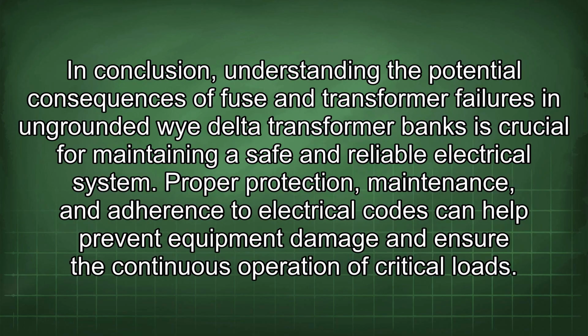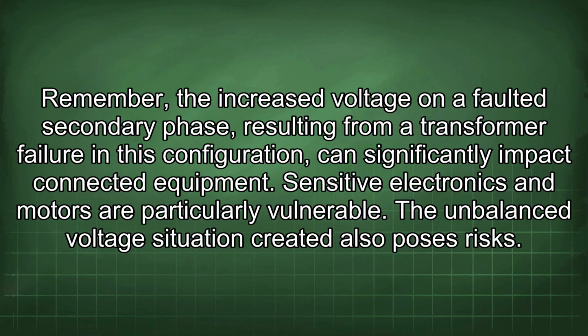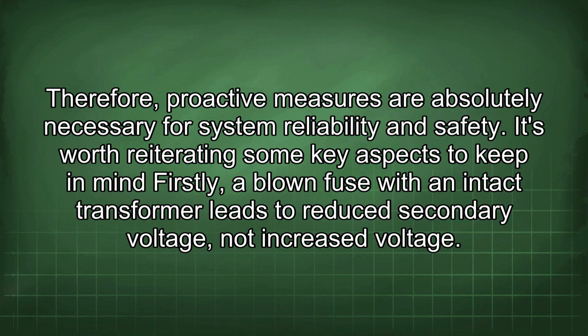In conclusion, understanding the potential consequences of fuse and transformer failures in ungrounded Wye delta transformer banks is crucial for maintaining a safe and reliable electrical system. Proper protection, maintenance, and adherence to electrical codes can help prevent equipment damage and ensure the continuous operation of critical loads. Remember, the increased voltage on a faulted secondary phase resulting from a transformer failure in this configuration can significantly impact connected equipment. Sensitive electronics and motors are particularly vulnerable. The unbalanced voltage situation created also poses risks. Therefore, proactive measures are absolutely necessary for system reliability and safety.